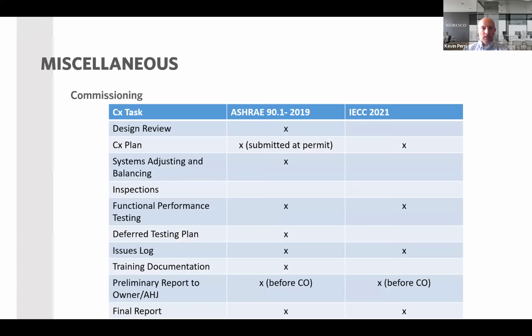The differences here in these tasks are that some are required to be submitted with permit and some aren't, or before you call for final certificate of occupancy inspection. So you can see a design review is required for envelope in ASHRAE pathway, but no design review is required in IECC. Commissioning plan is required in both pathways. However, you need to submit a commissioning plan with the permit set if you're following the ASHRAE pathway. So the commissioning plan is still going to get done. It's just one has to be submitted earlier than the other.